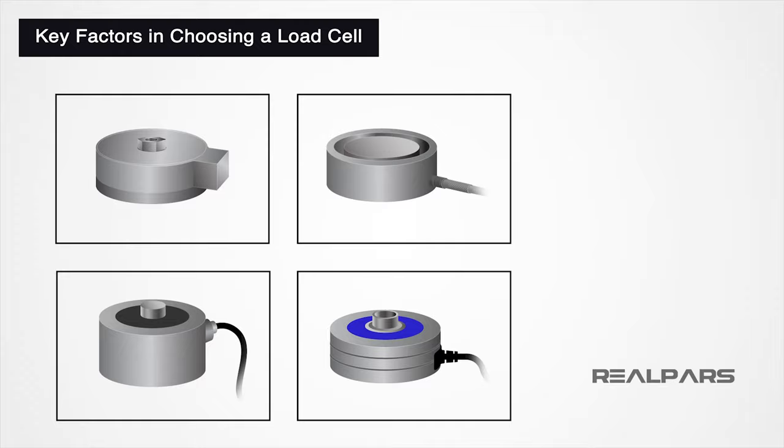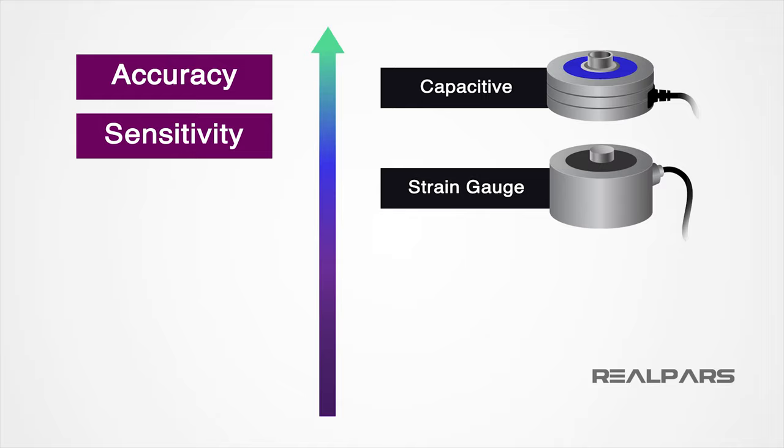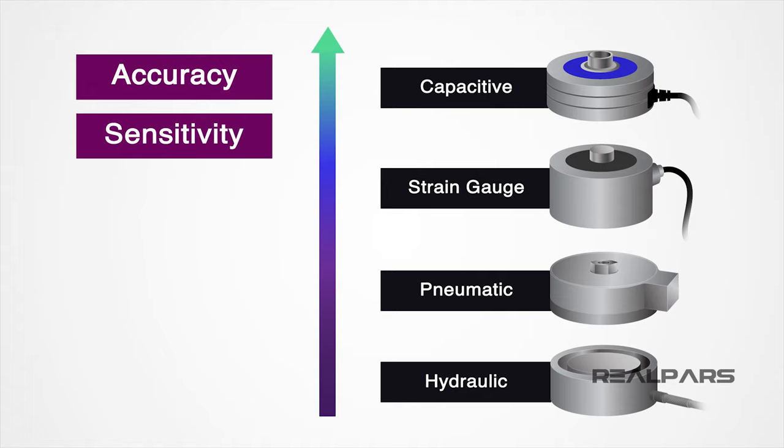Determining which load cell your application requires depends on how sensitive and accurate your application needs to be. The accuracy and sensitivity are very high with capacitive. A strain gauge type of load cell would be the next in line when it comes to accuracy and sensitivity. While still useful in certain applications, pneumatic and hydraulic load cells would be the least sensitive and accurate types.